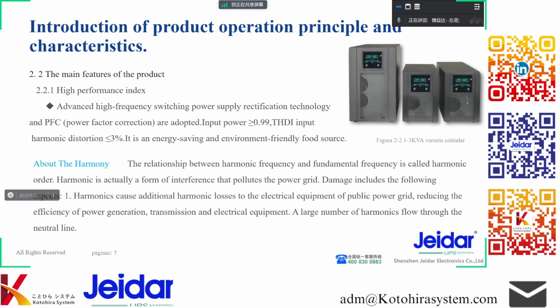The main features of the product: high performance index. Advanced high-frequency switching, power supply rectification technology and PFC power factor correction, with input power factor equal to or greater than 0.99 and THDI input harmonic distortion equal to or less than 3%. It's an energy-saving and environment-friendly power source.